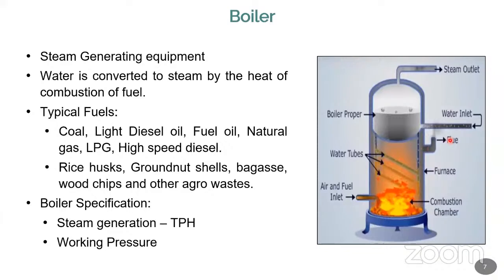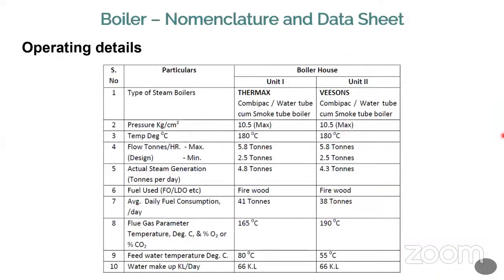Sometimes you need to evacuate the flue gas by a very convenient method. You duct out the flue gas because most of the time it contains ash. This is number 2. Number 3, you need a proper fuel and combustion chamber and combustion system to produce the necessary heat. So that is another important point that will be taken into account. We will discuss those points later. No problem. So this is the normal nomenclature, or the detailed specification, of a boiler.